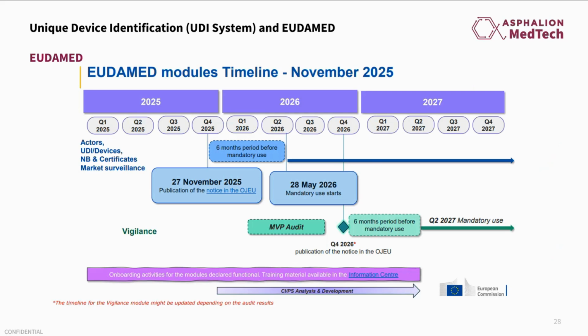incidents. So this EUDAMED database has been a really ambitious project by the European Commission, and it is now also in a transition stage. So far, we have this date, May 28th, which should be the date that will define the mandatory use of the device registration module for those newly MDR certified devices. That means that if you have a medical device certified after this date, you then need to automatically register your device in the EUDAMED database. For those devices that already have the CE mark before this date, there is a transition period until November this year, but it's really important that you start preparing to comply with these registration requirements in this database.